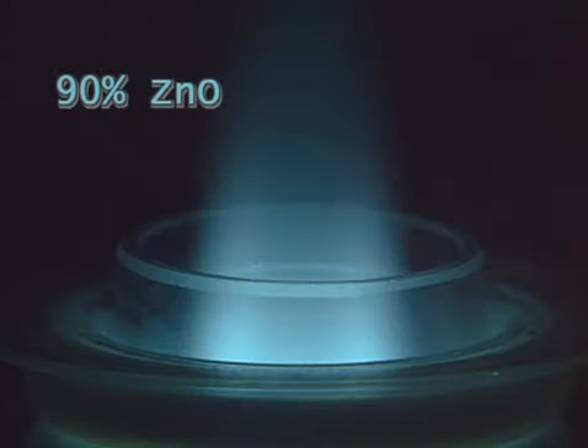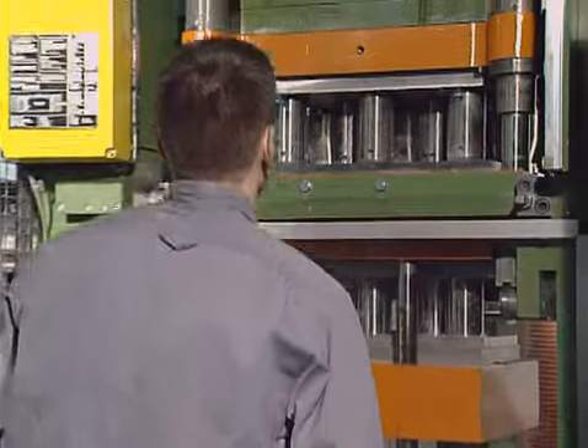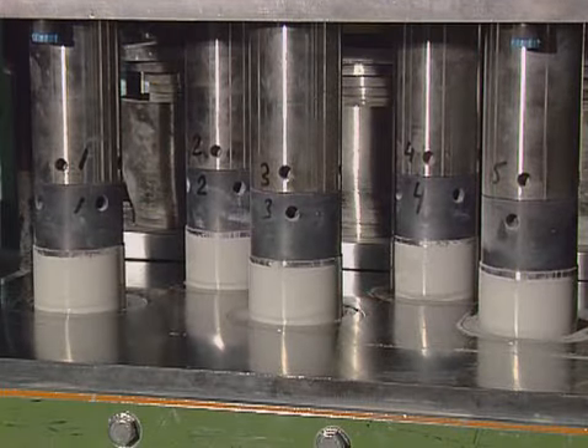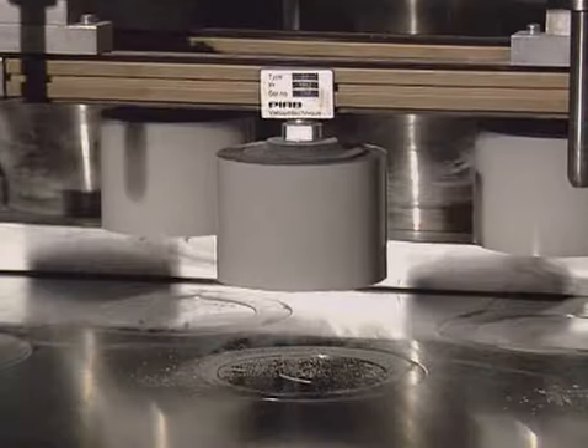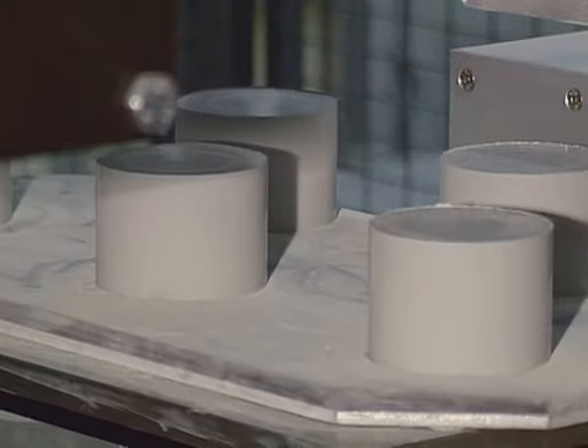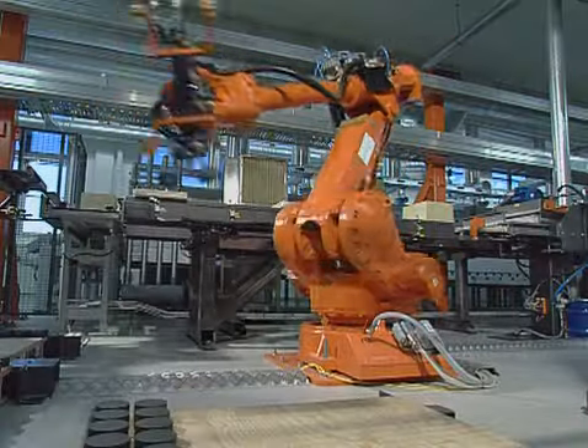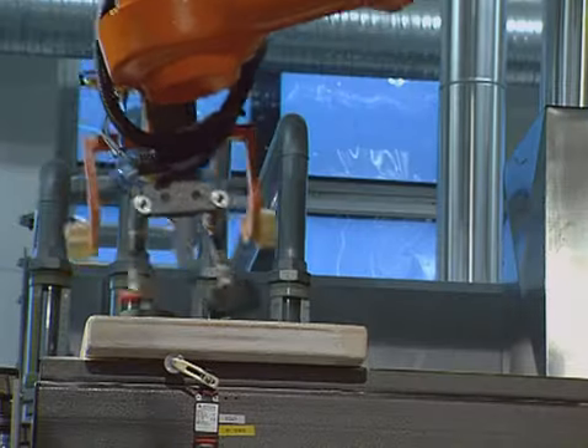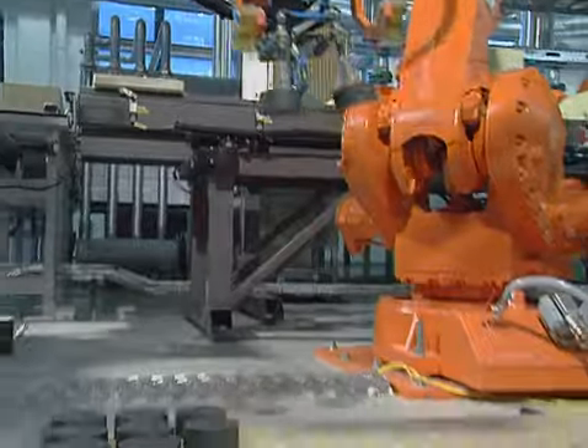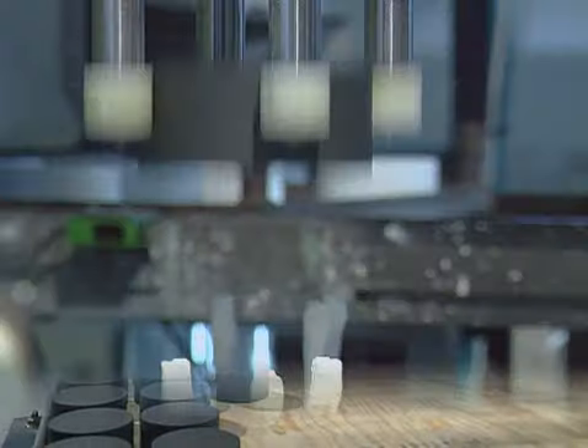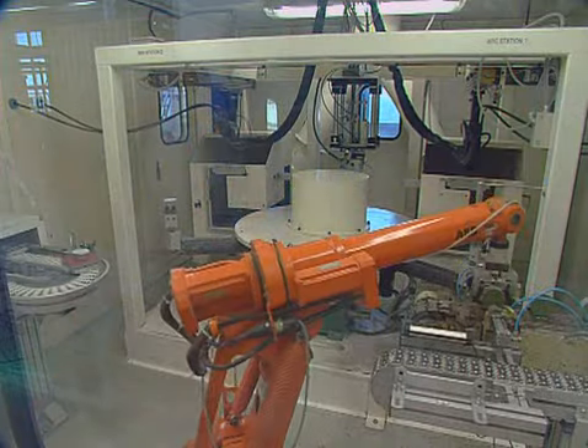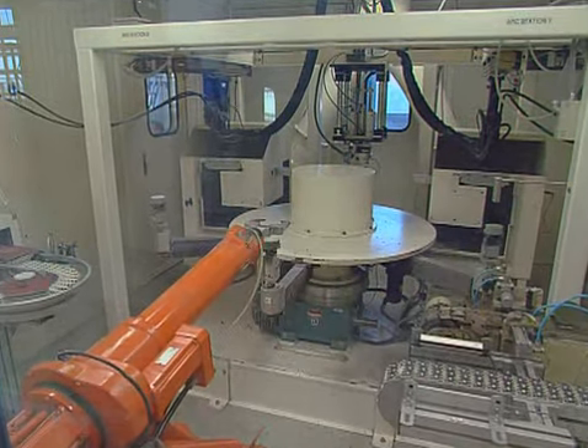The primary component is zinc oxide. The powder that is produced is pressed into blocks under high pressure. A sintering process follows. During this process, the block gets smaller and changes color. An insulating coating is applied to the outer surface. The blocks are heat-treated, after which a thin layer of aluminum is applied to the electrode surfaces in order to obtain good electrical contact between the blocks.